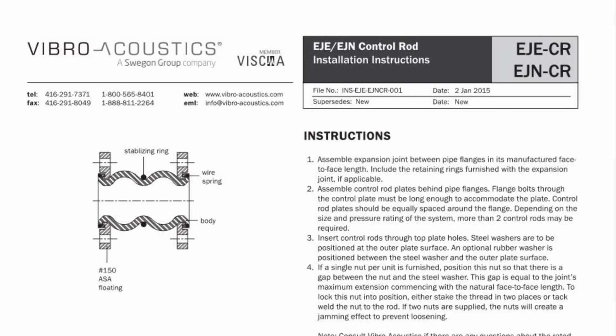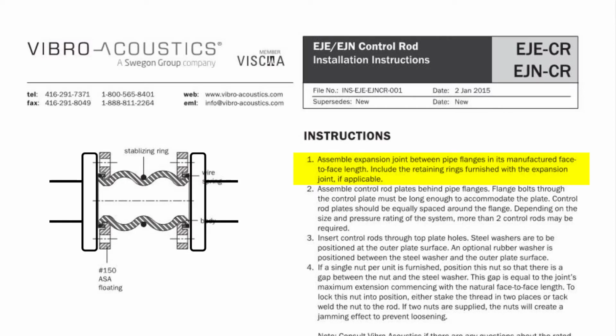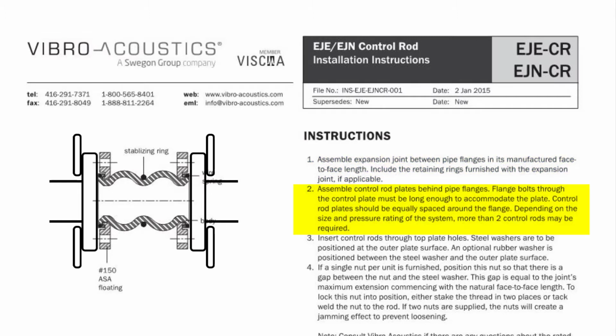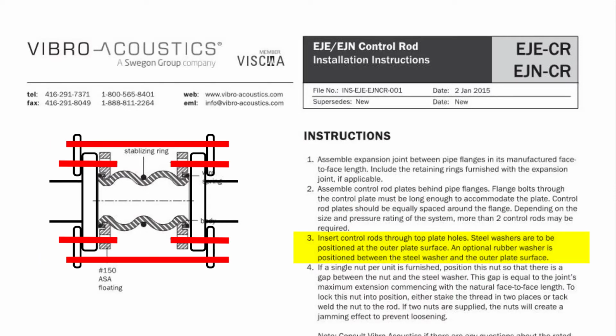Here are the installation instructions again. We're going to look at the second page now, which describes how to install an expansion joint with control rods. The expansion joint must be installed between the pipe flanges first, as we previously described. Next, the control rod plates need to be attached, equally spaced around the flanges, with bolts that pass through the plate and both the pipe flange and the joint's floating flange. Next, the control rods need to be inserted through the corresponding holes in the plates, complete with steel washers, rubber washers, and nuts.